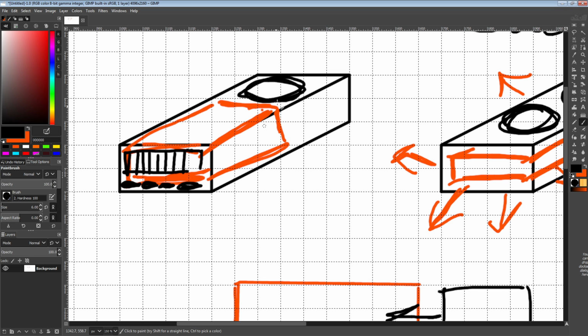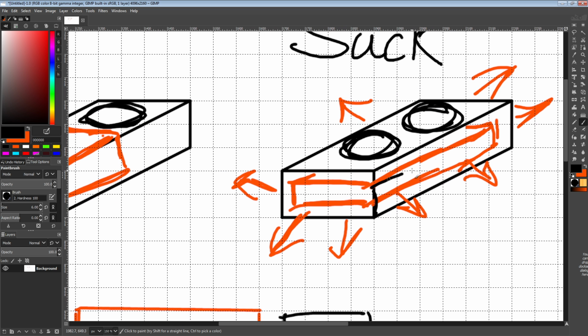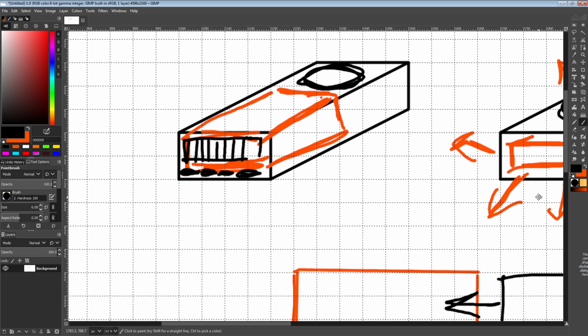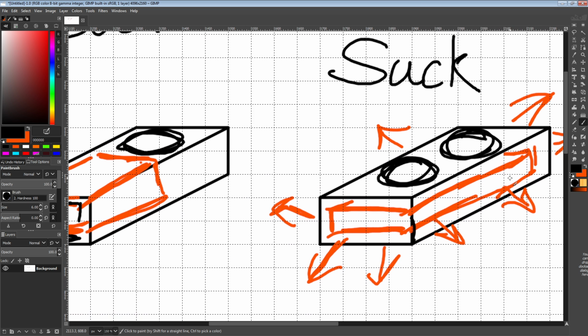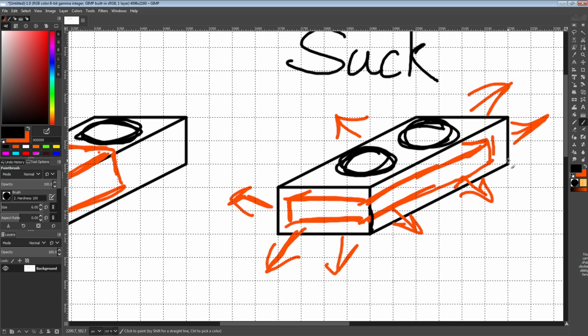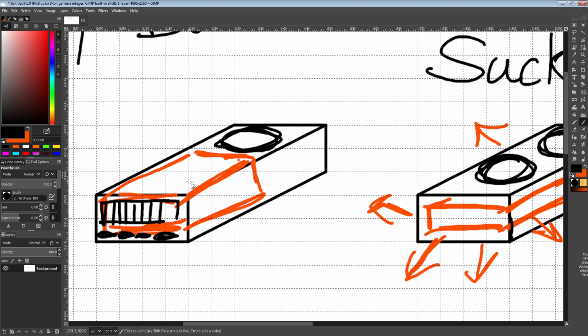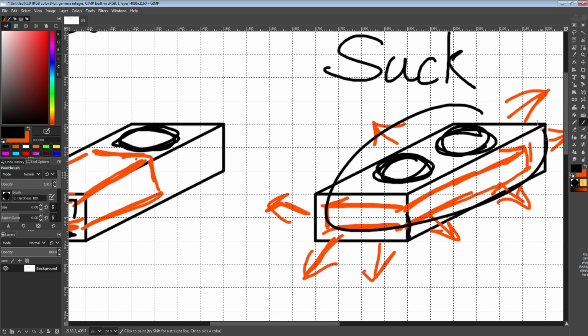So the first problem we run into is this has maybe 8 to 10 times as much open exhaust area - I'm not going to do the math on that. But the main point is, because this has so much more open exhaust area, to get the same amount of airflow, if it has say 10 times as much exhaust area, you need 1/10 the airspeed to get the same airflow through the heatsink.